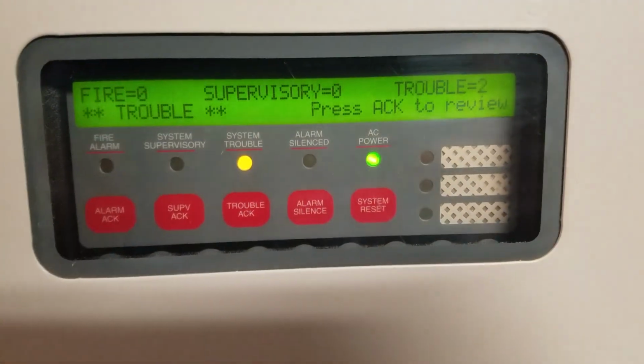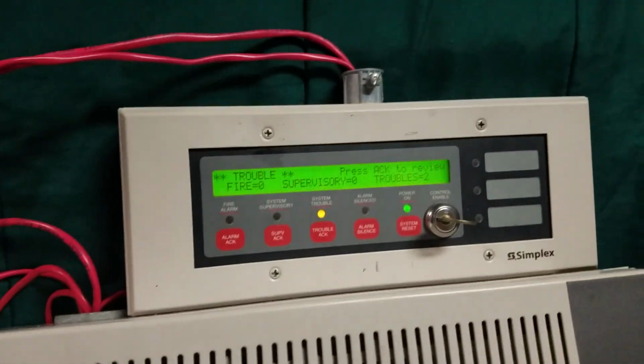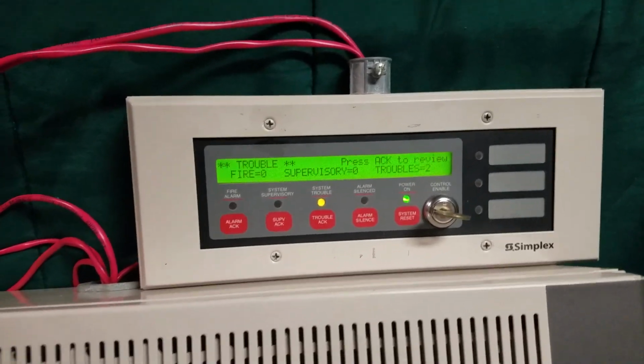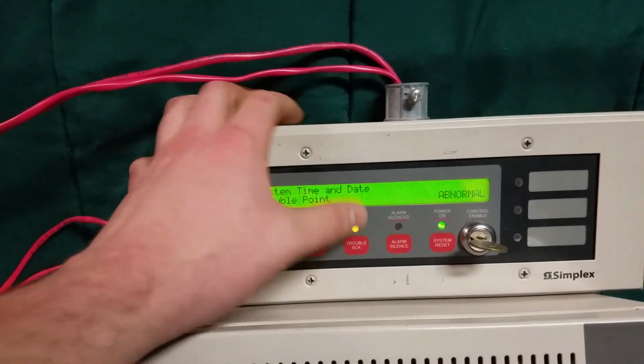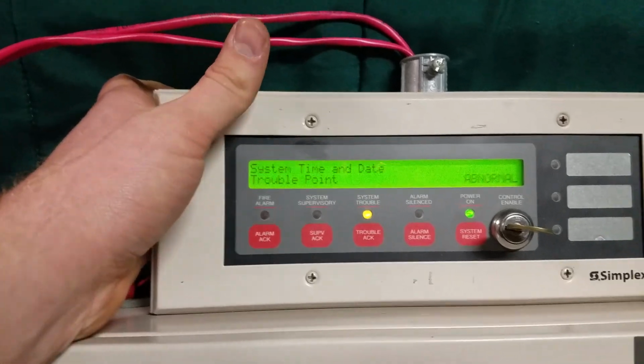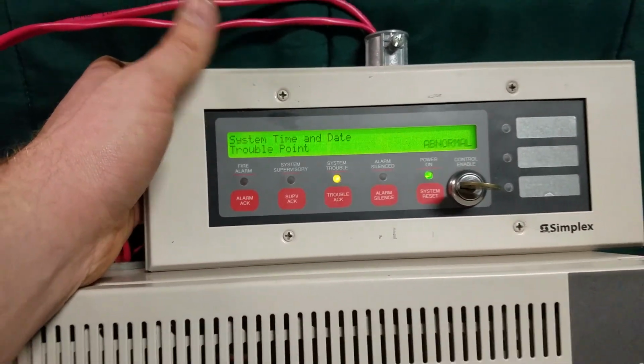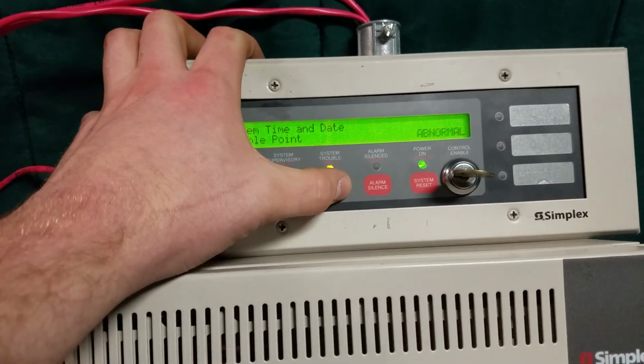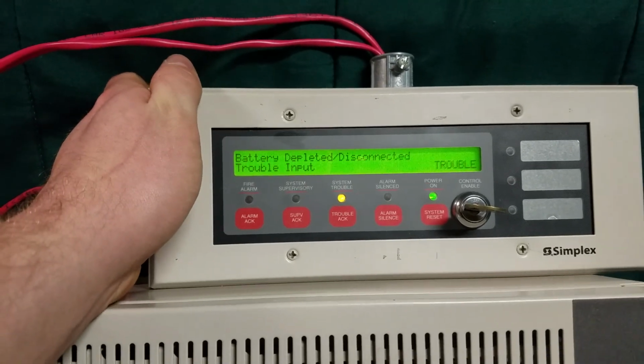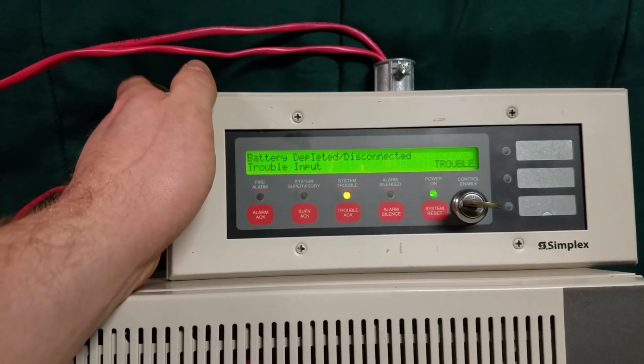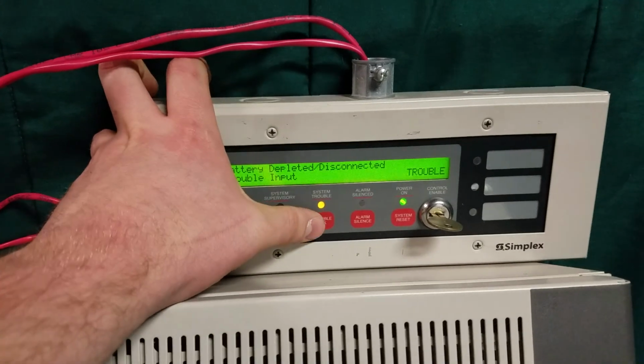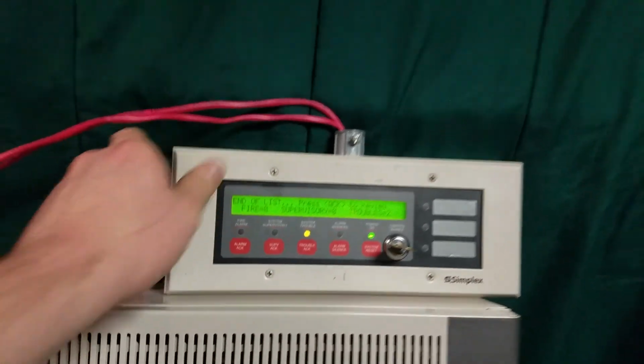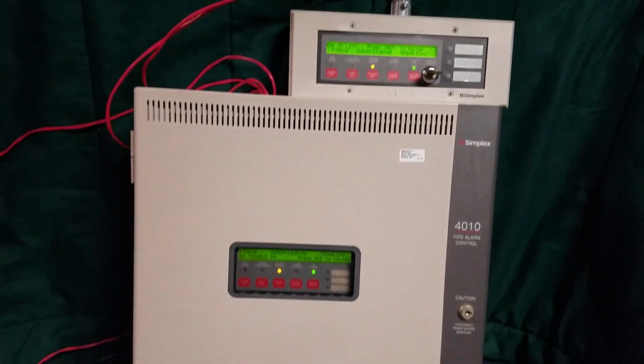So the panel, it does have two troubles. We're actually going to be using the annunciator to control everything today. Let's go ahead and go through those. The first one is a very easy fix, system time and date. It's just because I simply haven't set it. Second one, also pretty easy. It just simply doesn't have batteries. Other than that, the panel is normal.